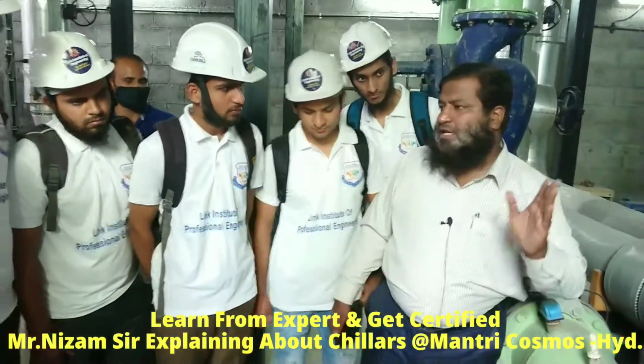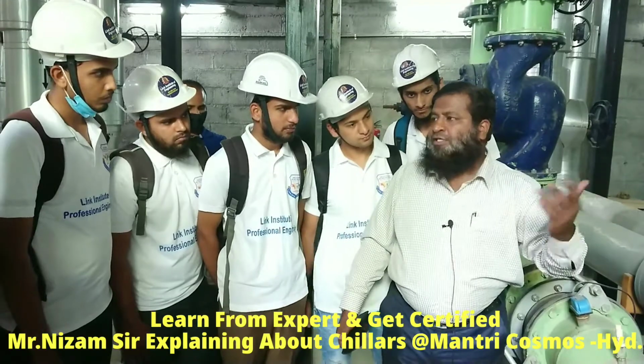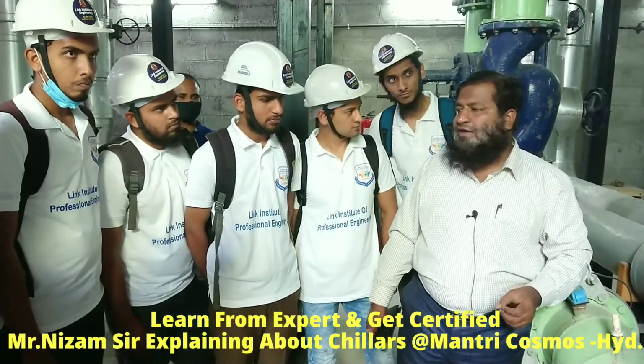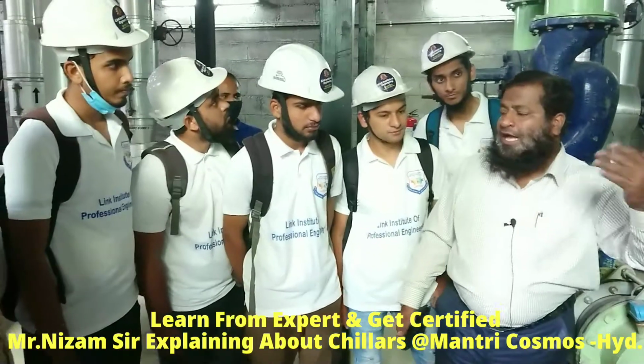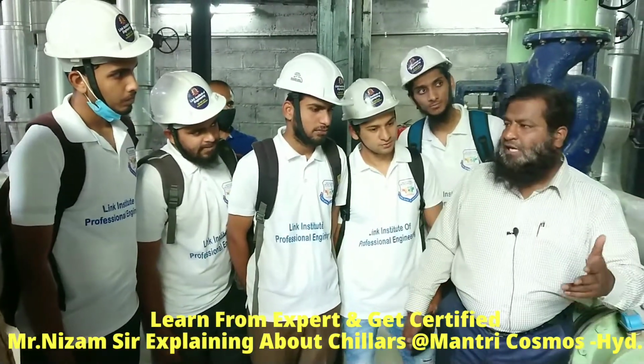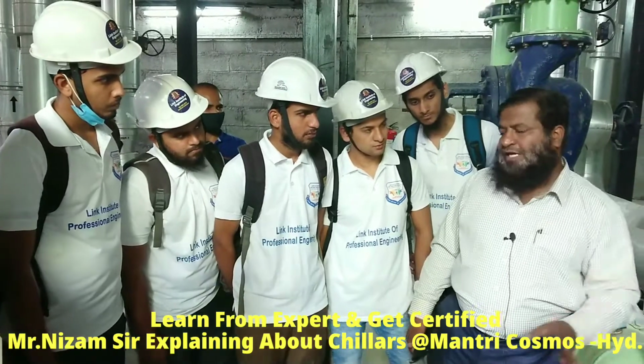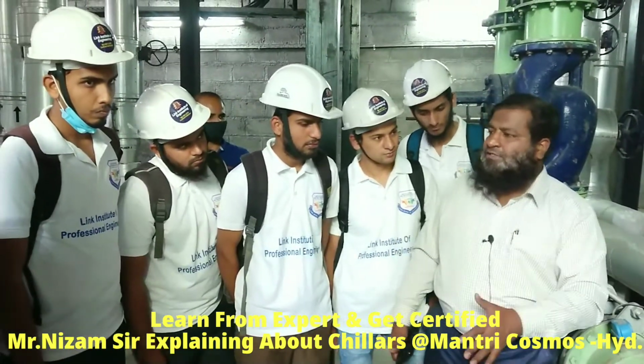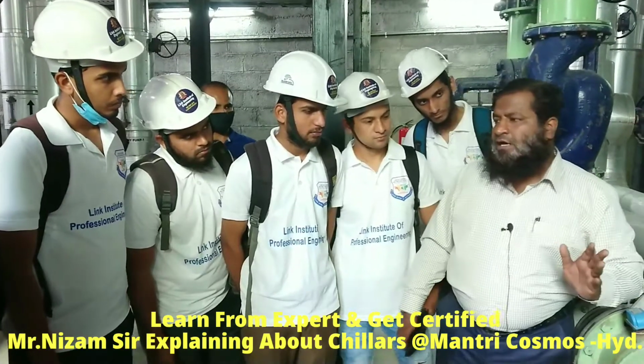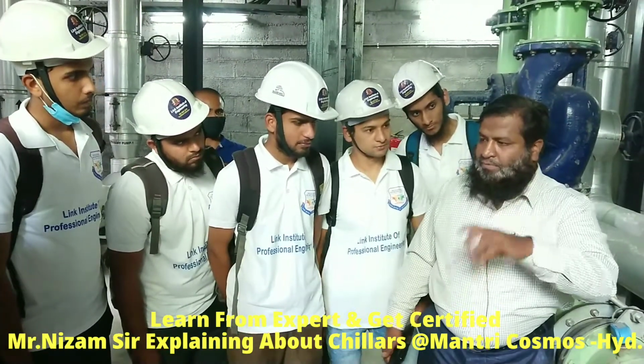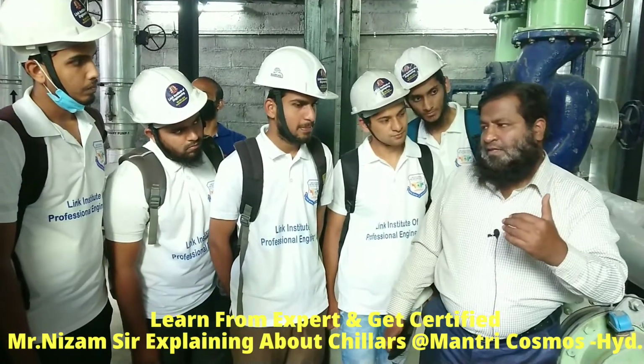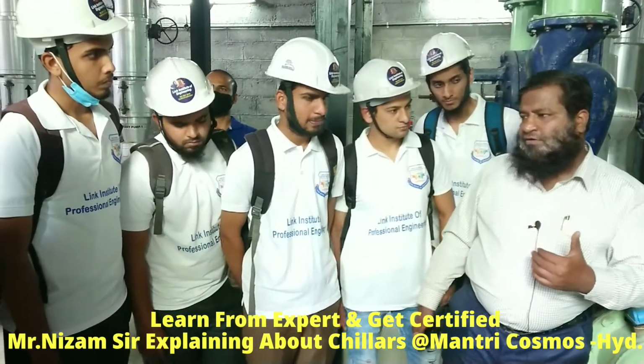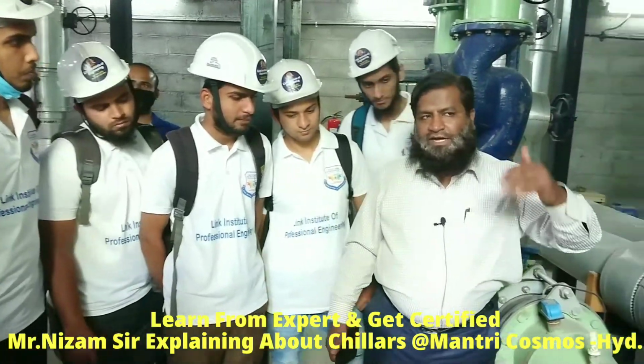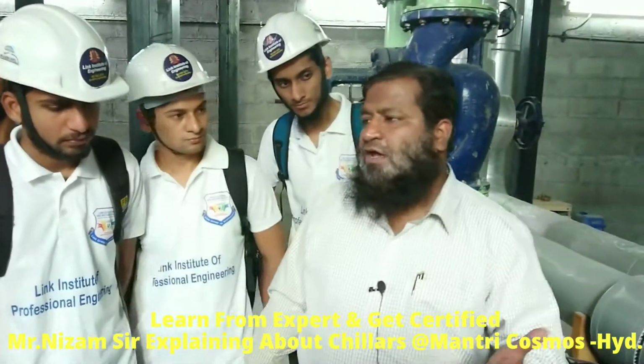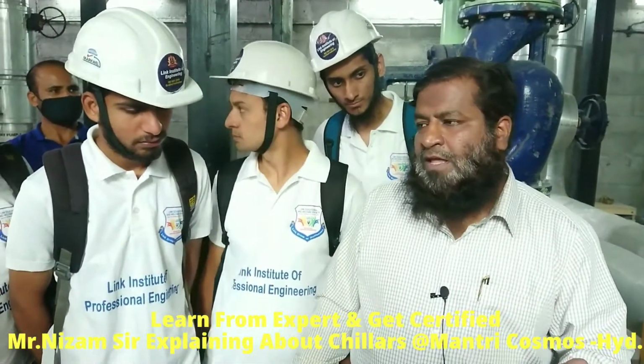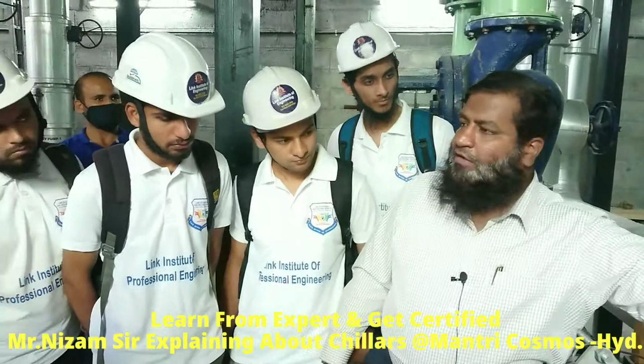and then it goes to the expansion device, where expansion of the refrigerant happens. Expansion means the pressure gets reduced; we can call it a pressure reducing valve, a throttle valve, or an expansion device. So the medium pressure, medium temperature liquid refrigerant, after getting condensed in the condenser, goes to the expansion device, where the pressure of the refrigerant reduces, and as the pressure reduces, the temperature also reduces. Simultaneously the expansion device also works as a valve which can control the flow of the liquid, so that overflooding should not occur at the evaporator stage, which is the main chiller.